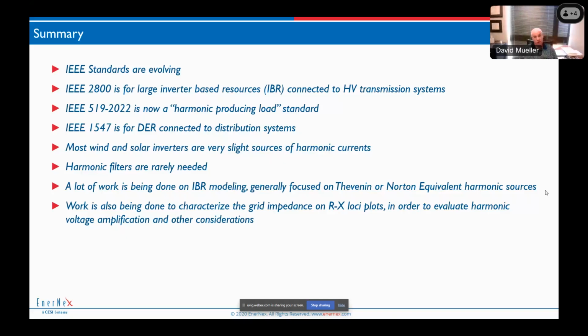Most wind and solar inverters are actually pretty good power quality citizens. They're very slight sources of harmonics. That's because the converters are multi-level modular converters that are designed to have very low harmonics. Yes, they have high frequency switching noise, but by the time we see that impact up on the transmission system, it's a very slight source of harmonics. For most projects, we don't need harmonic filters.